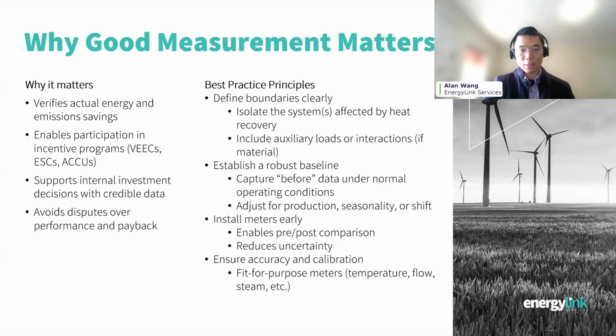So secondly, you want to establish a robust baseline. You want to adjust for variables like production or seasonality, and then you want to use meters that are fit for purpose, as I mentioned just earlier. You want to look at steam flow meters or temperature sensors. You want to install them early to capture both the before and after data, so you can then compare apples with apples a bit later.